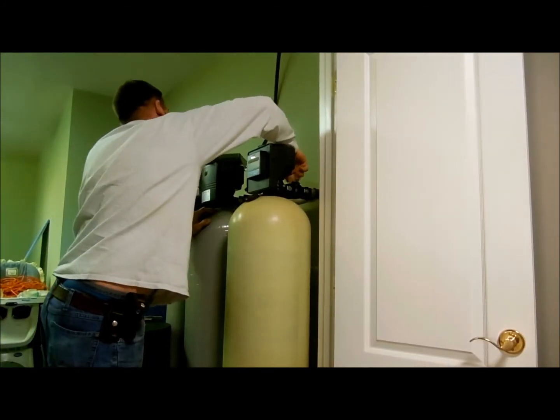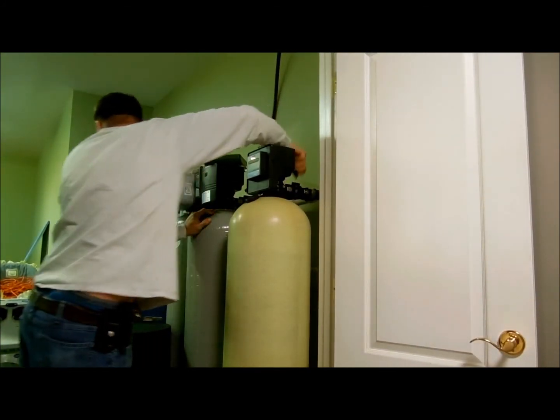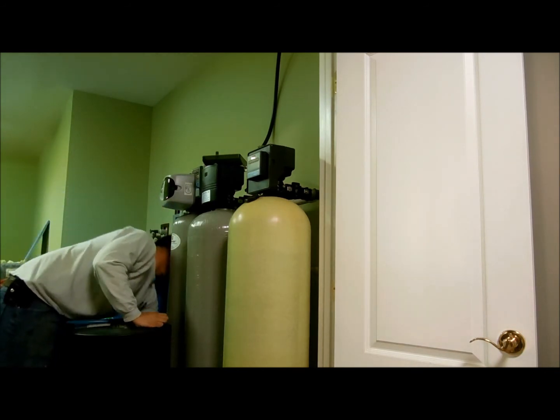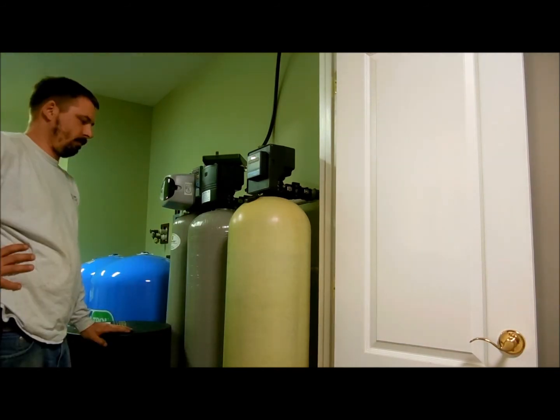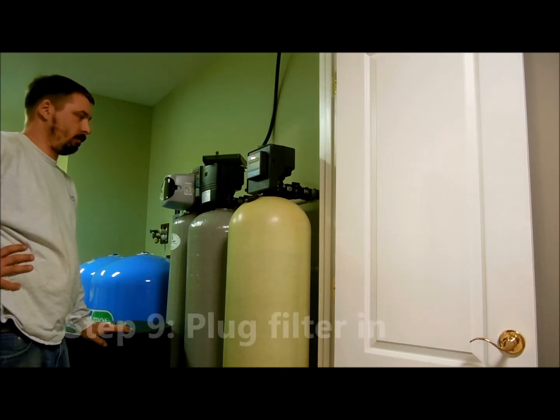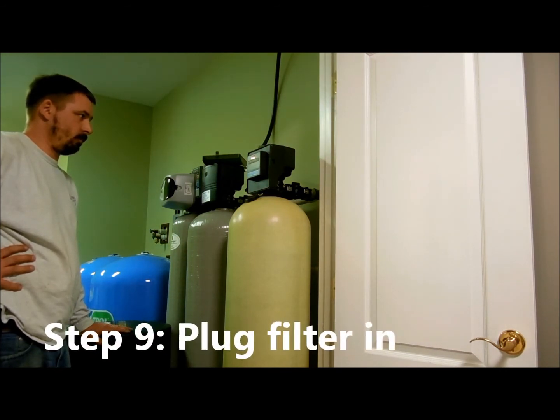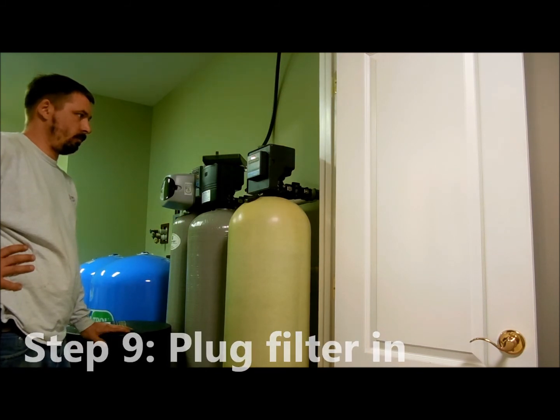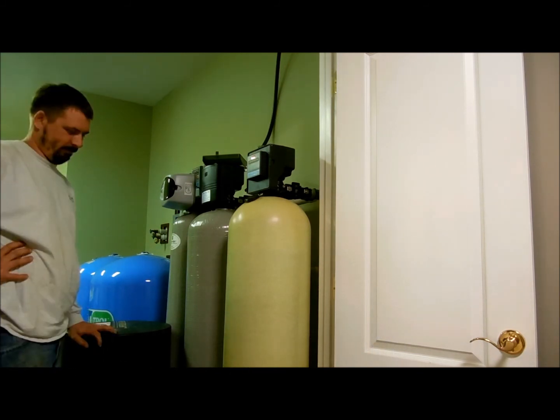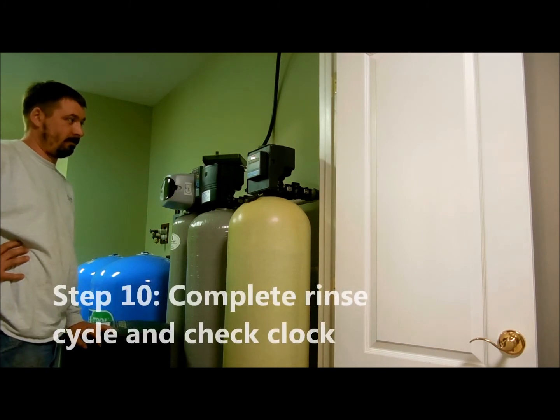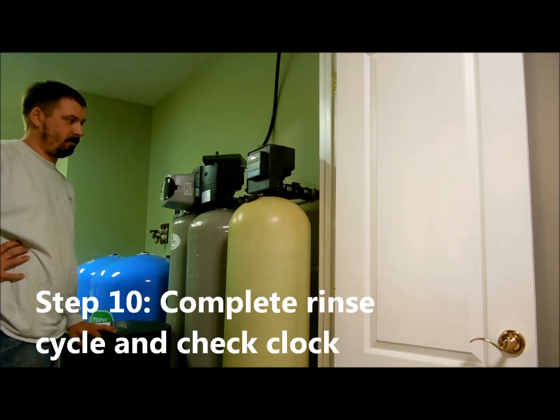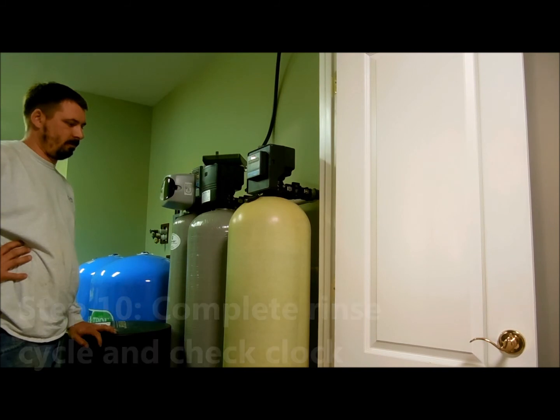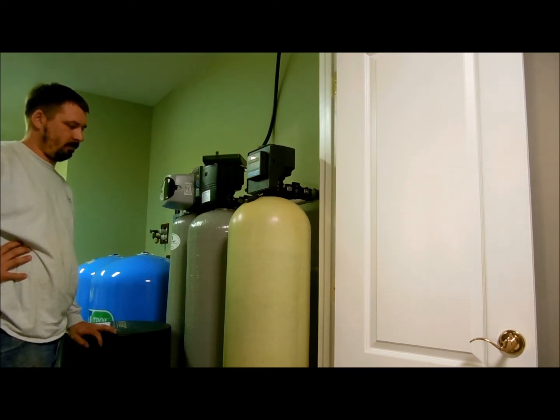After a few minutes on half speed, open the bypass fully to allow the filter to finish the backwash cycle. Once you've allowed the filter to backwash on full speed for 5 minutes, you are ready now to plug your filter back in and advance the cycle to rinse. Skip ahead to the rinse cycle on your filter to settle the bed and clear the water up. I usually let it rinse for its full amount of time so that it makes the water as clear as it can be when I turn it back onto the house.